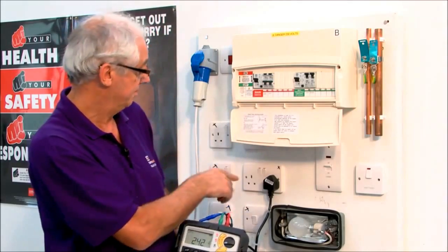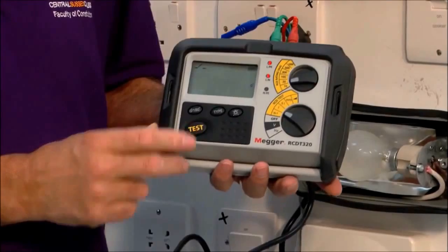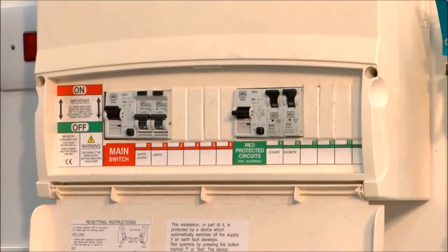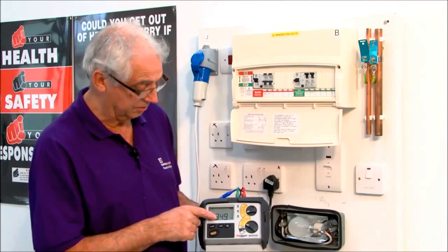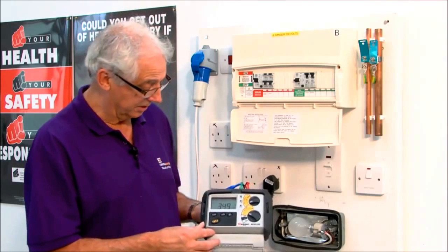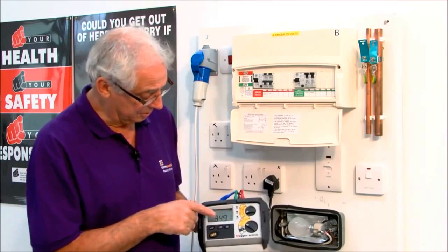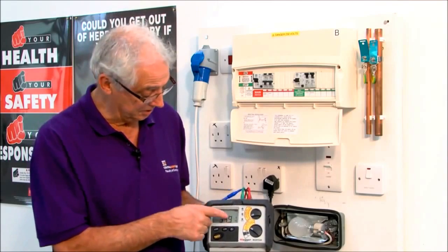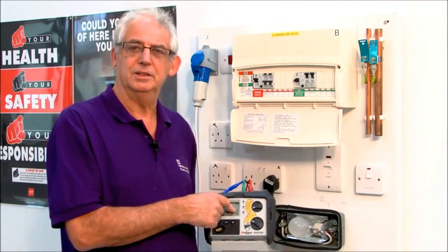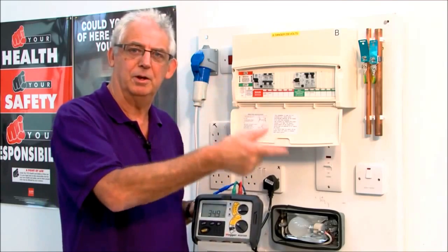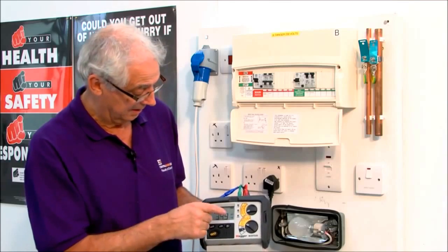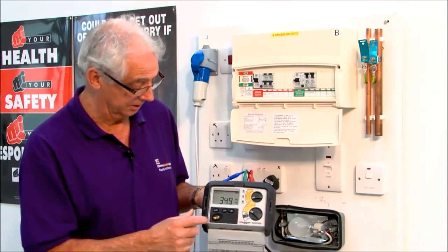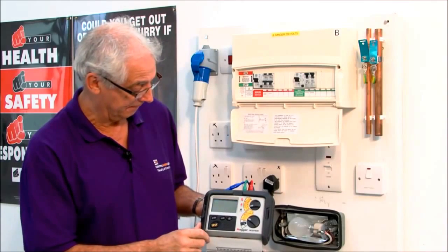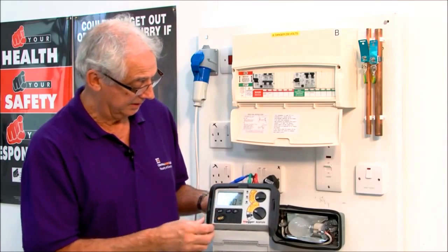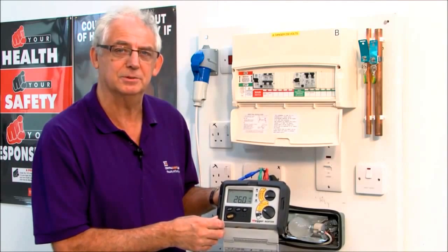Because this is a BS type. Push the button. It's tripped within 200 milliseconds, it's 34.9. So perfectly okay, less than 200. But of course, that's only on one side of the waveform. If you see, that's got a 0 there. What I really need to do is test the current going both ways. So I push this button here, and now it's telling me it's 180 degrees. Turn the RCD back on again, push the button. Again, it's tripped within 26 milliseconds, which is really quick.